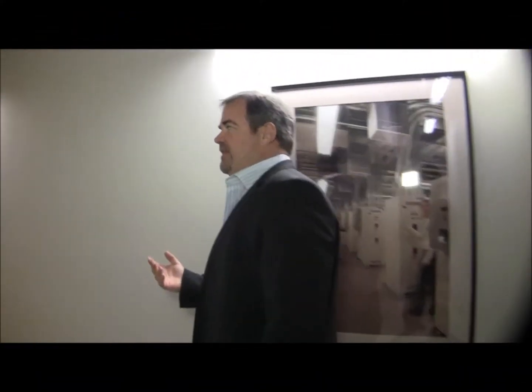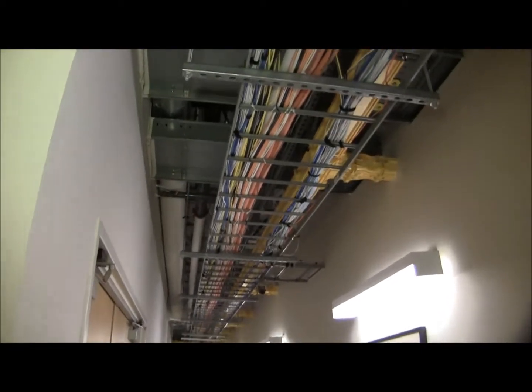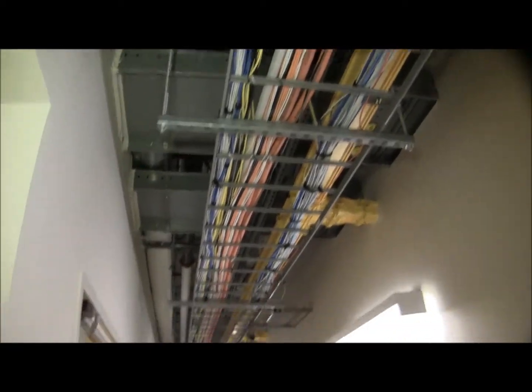Once you're on the customer side of the area, at each one of the doors there are CCTV cameras, which are monitored 24/7 by our staff. There's one in the front of the door, there's one on the back of the door. We record these cameras and we see them constantly. And to get into the facility, you have to have an HID accepted card. If there's a change of employee status at a company, we can shut these off with a moment's notice through our NOC. We open up a trouble ticket and can allow access for people in and out.